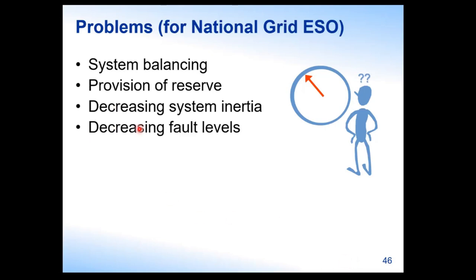Decreasing fault levels is another technical issue. Synchronous generators, traditional generators, provide a significant fault current if there's a fault on the system. You may think that's a bad thing, but actually it's needed to make electrical protection systems work, to allow voltage to recover after a fault. The power electronics from wind turbines, from HVDC converters, and from solar panels don't provide anything like the same infeed. So it's a difference in the characteristic of the generation source that causes the problem on the system.